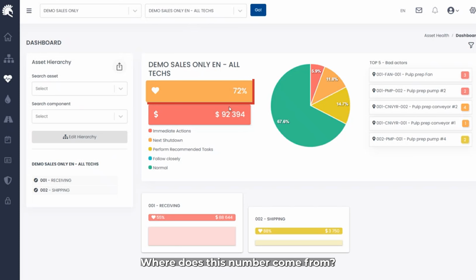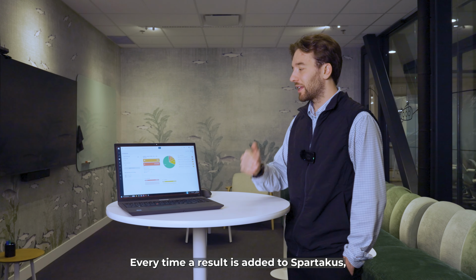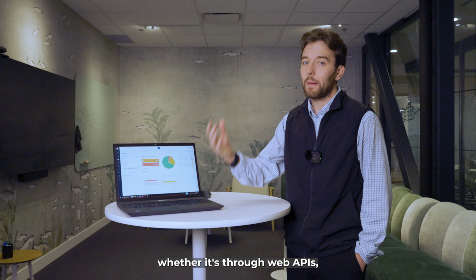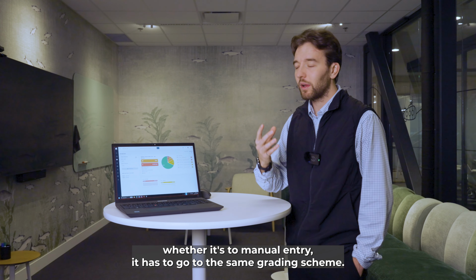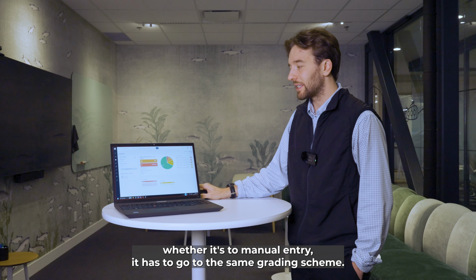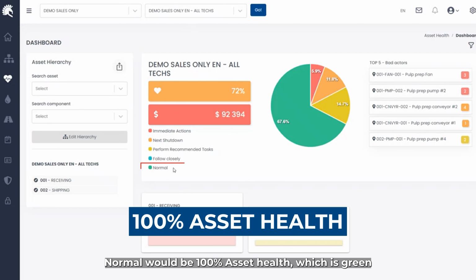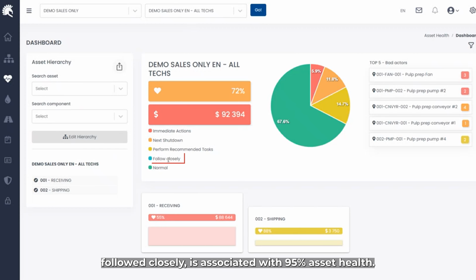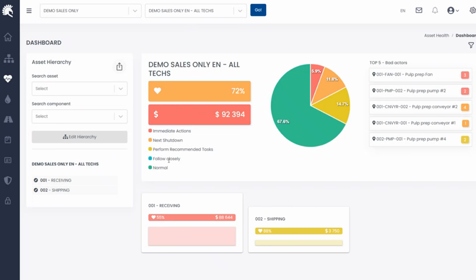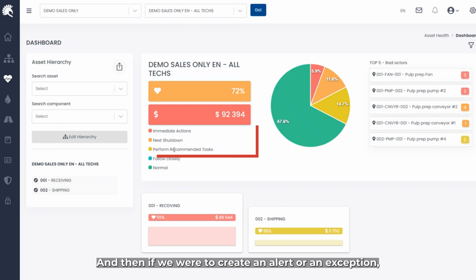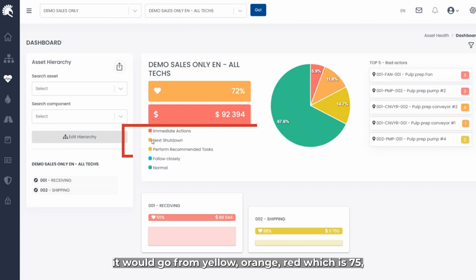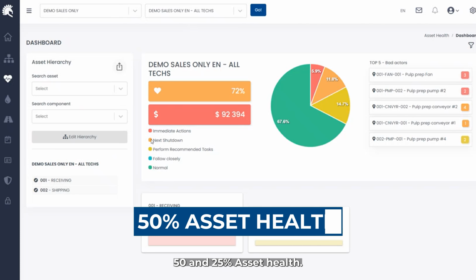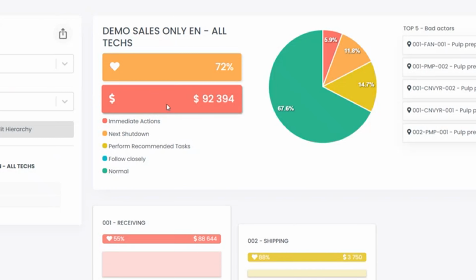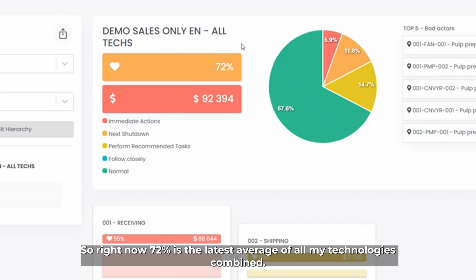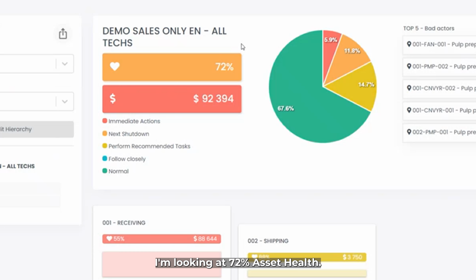Where does this number come from? Every time a result is added to Spartacus, whether it's through web APIs, automatic entry, or manual entry, it has to go to the same grading scheme. Normal would be 100% asset health, which is green. Follow closely is associated with 95% asset health. And then if we were to create an alert or an exception, it would go from yellow, orange, red, which is 75, 50, and 25% asset health. So right now, 72% is the latest average of all my technologies combined.